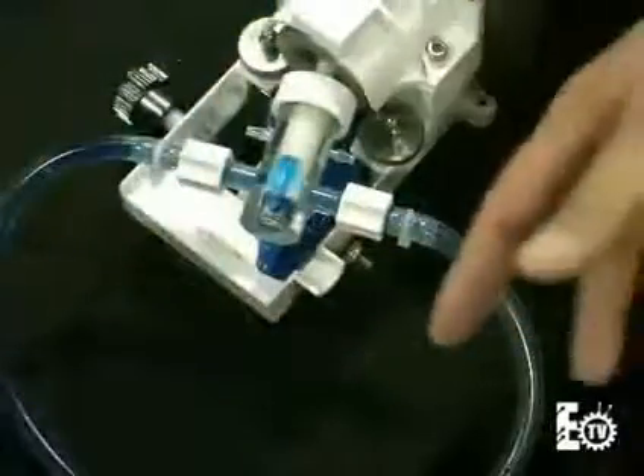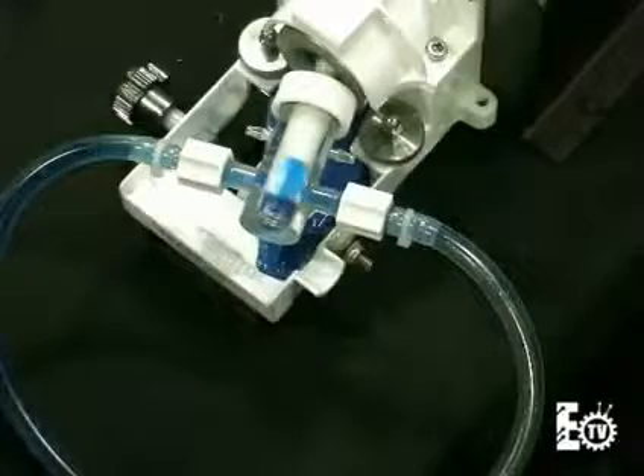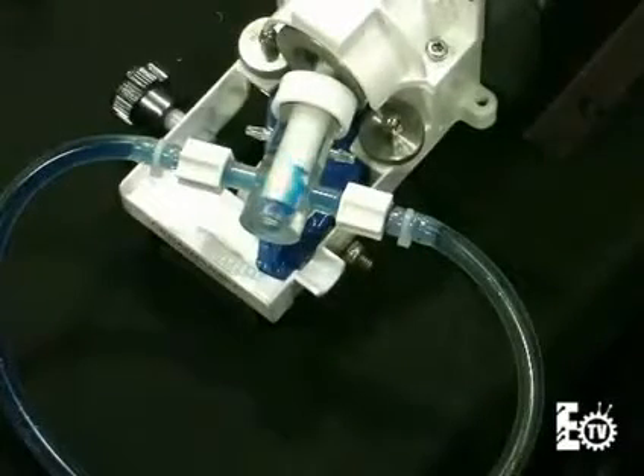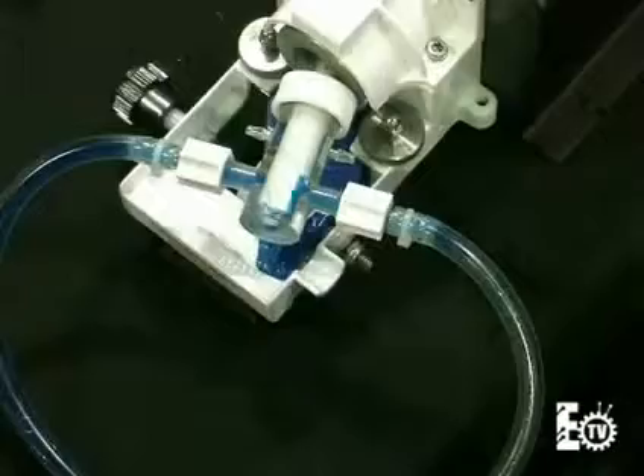The main thing is not to cavitate our pump. So our inlet side is the most important. Discharge, because we are positive displacement, doesn't matter. As long as there's enough power with the motor, it'll overcome it. What kinds of things would cause cavitation?